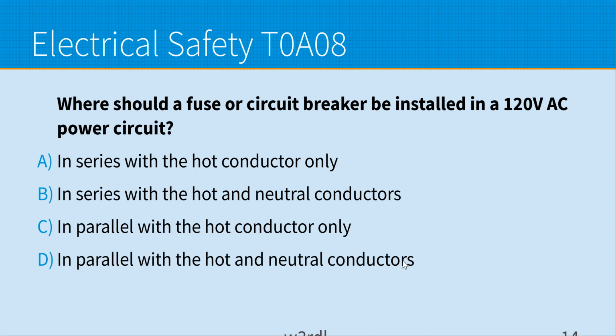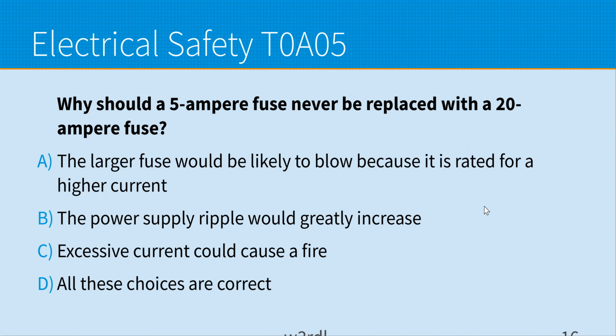Where should a fuse or circuit breaker be installed in a 120 volt AC power circuit? I don't think I talked about that either. It's there somewhere. Yeah, in series though, with the hot one. Right. In the hot conductor only, not on the neutral. And in series, not in parallel. These two parallel are definitely throwaways, because if you do it in parallel, it's kind of pointless. It does nothing. It's like, oh, look, there it goes.